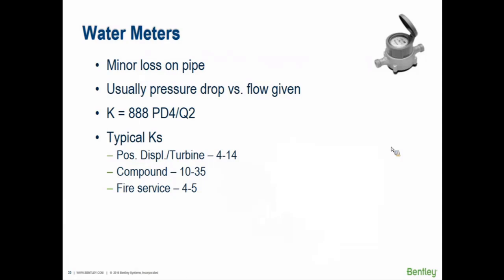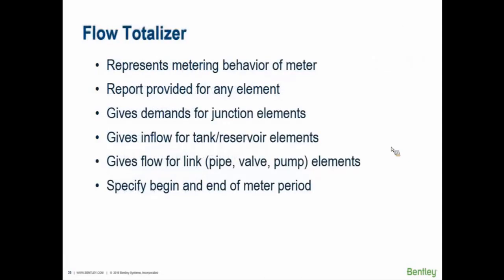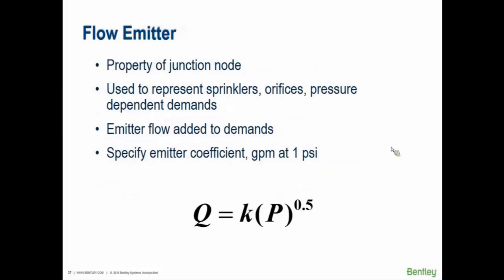Water meters generally don't require modeling of head loss through them since that's the customer handoff point, though you can apply a K value from the meter manufacturer catalog if needed. Flow totalizers can track the total amount of flow through any element over time. Flow emitters — for things like sprinklers or irrigation systems — allow water to exit the system, and we'll discuss those more during the fire flow presentation.